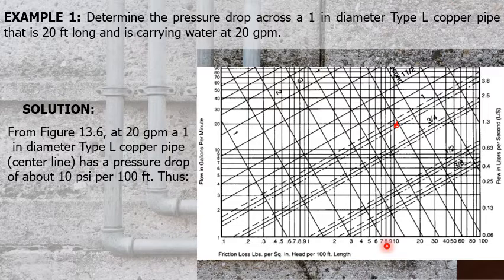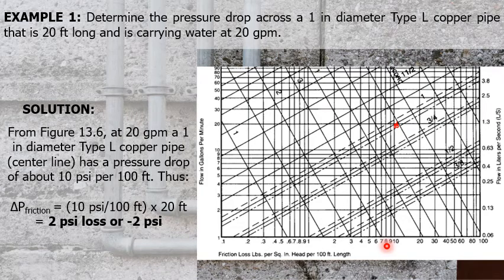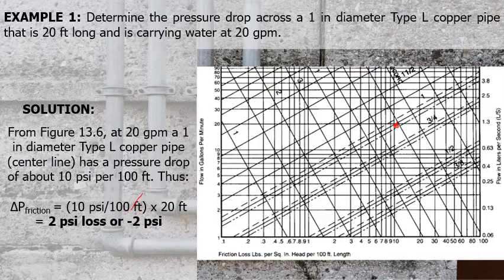From Figure 13.6, at 20 GPM, a 1-inch diameter type L copper pipe has a pressure drop of about 10 psi per 100 feet. Thus, to compute for the pressure drop of the problem, we simply multiply 10 psi per 100 feet with the length of the pipe, which is 20 feet, so that this unit will be cancelled. Calculating, that is equal to 2 psi loss, or negative 2 psi, which is the pressure drop.